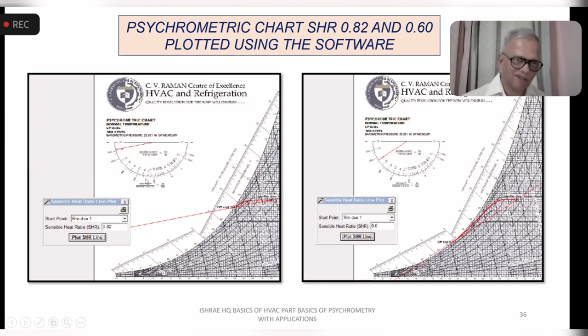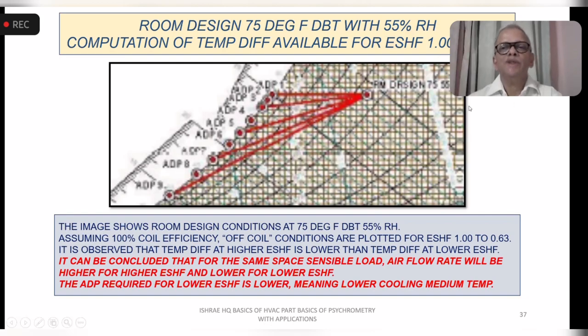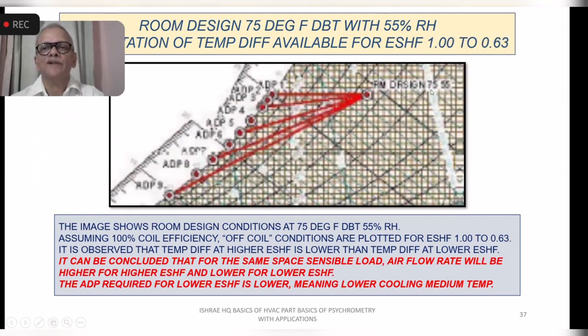Now, what you see here as the sensible heat factors, this is the feature of the software. Now see, this is the room design condition. Here I have taken 75 degrees Fahrenheit dry bulb temperature and 55% RH. That is the point. And what I have done is I have tried to select the ADPs depending on the sensible heat factor, which was available from the table which we saw sometime back. So a horizontal line means a sensible heat factor of 1. The entire amount of heat to be removed is sensible.